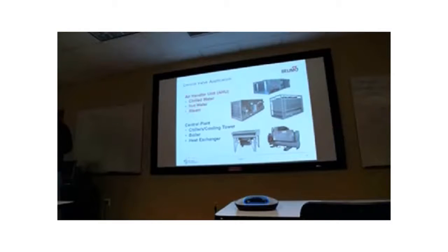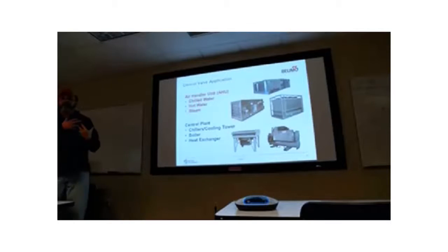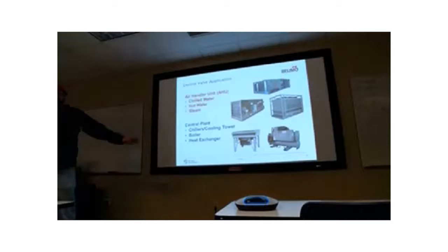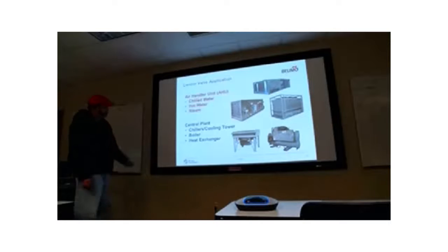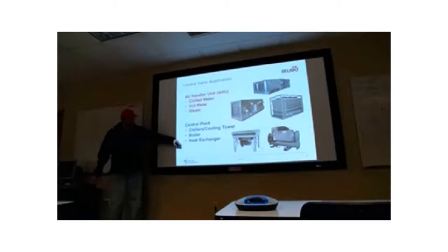Like chiller plant or your boiler plant. Yeah, but what is it? When I say plant, what equipment am I referring to? I'm referring to the machinery that converts the energy, right? A chiller has a motor, and it basically produces the energy that the distribution system puts all over the place. So when you talk about the plant, you're talking about the heart of the system, the chiller or the boiler, that kind of thing. Okay. So we have heat exchangers too, which can be considered part of the plant.